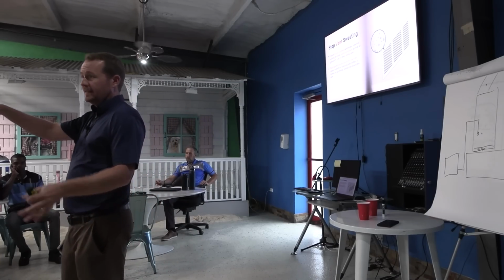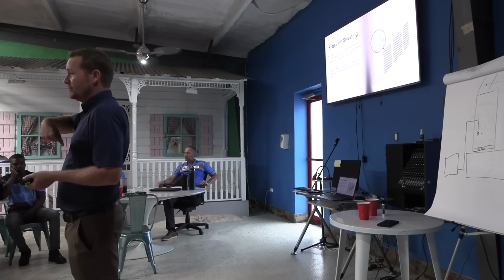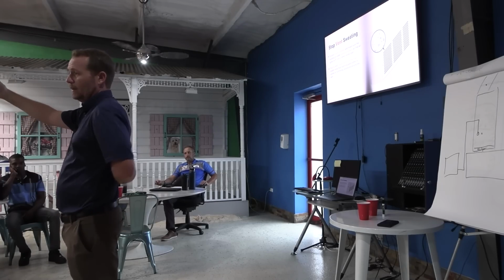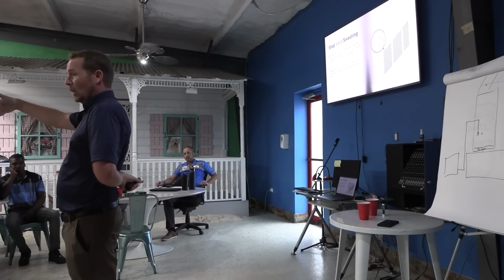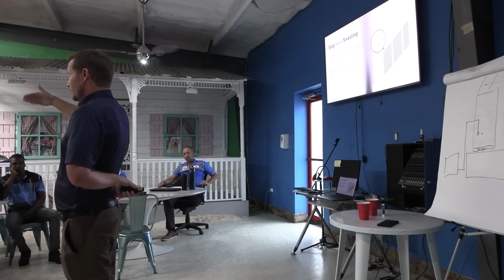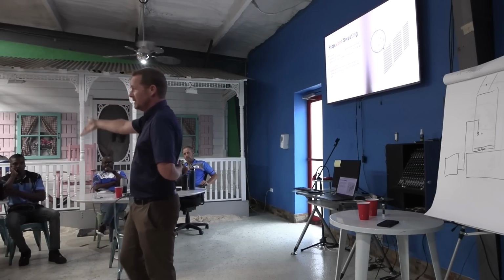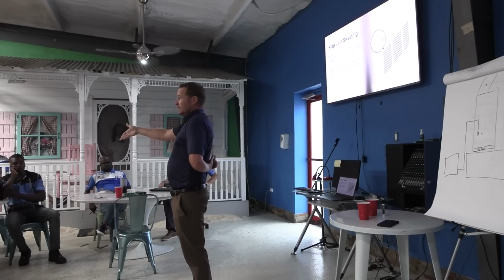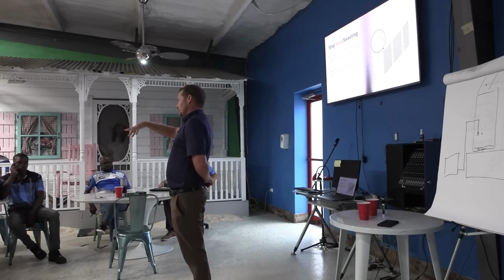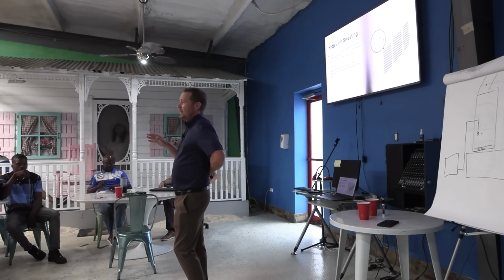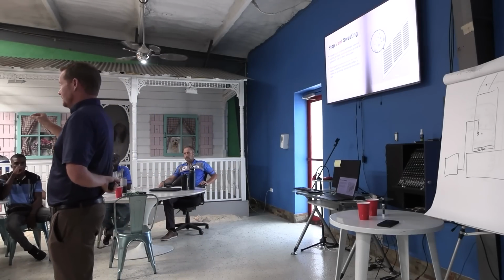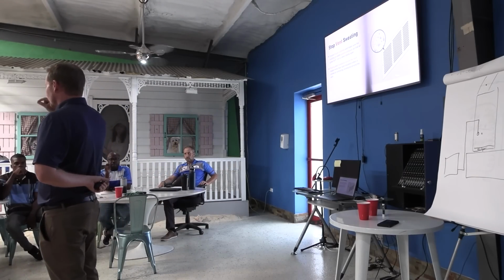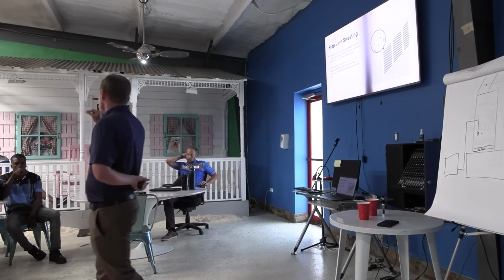Put a dehum in, so this is what a dehu does. This is the thing that a lot of people miss. It's not just that it pulls out moisture, but if you put your hand in front of a dehumidifier, what does it blow out? Hot air, warmer air, right? So it's hot. So it adds to the load, which increases the runtime. Like this is why, and I don't know that Evolution still has this, but Carrier for the longest time had the option where you could actually do reheat with electric heat strips on these systems in order to help reduce humidity. You could literally run electric heat to reheat to increase runtime.